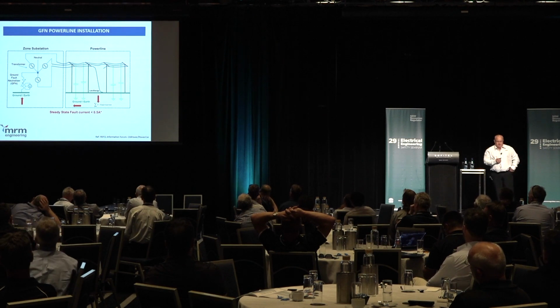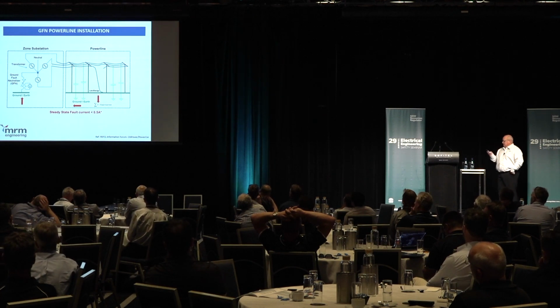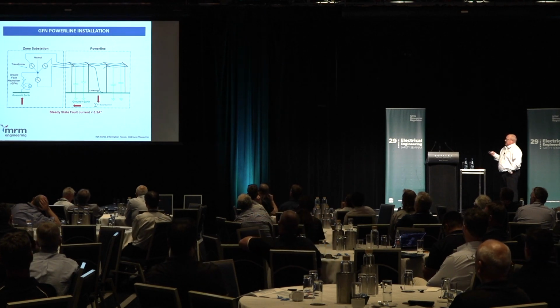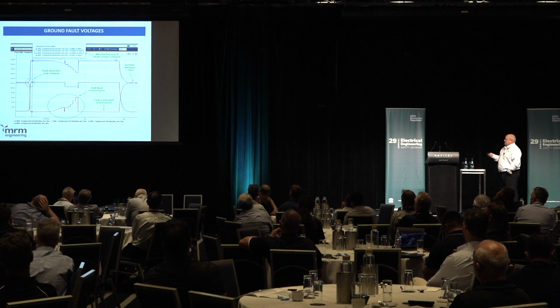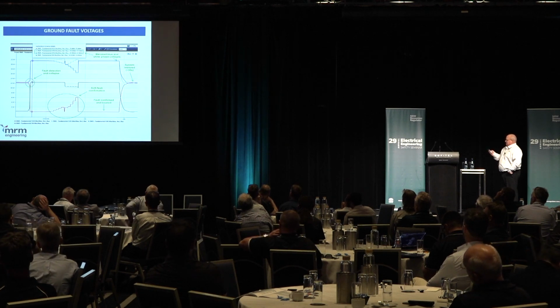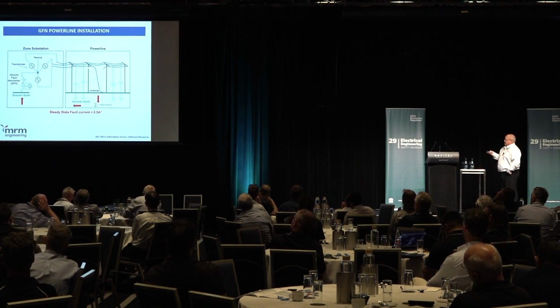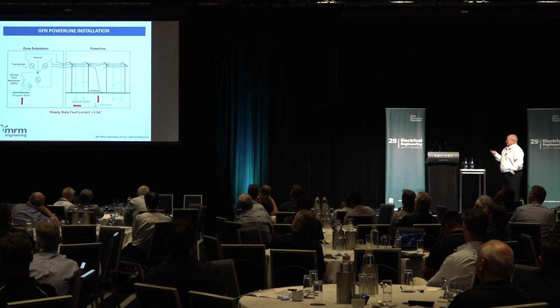So this is just a diagram. This one shows now the capacitance through the ground. The residual current compensation on the previous diagram cancels out any ground fault currents associated with that. And then the ground fault neutraliser. So with the ground fault neutraliser, you can see there's no spark there because the inductance has matched the capacitance and the fault currents to actually cancel the fault.